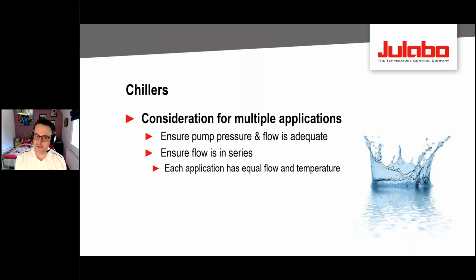That's the first thing you need to think about. The second thing is to ensure the pump is up to the job. If you're feeding one glass condenser, a simple 1 bar pump is easy. If you're feeding 4 or 5, you may need a 2 or 3 bar pump. But also think not just about pressure, but about flow rate.